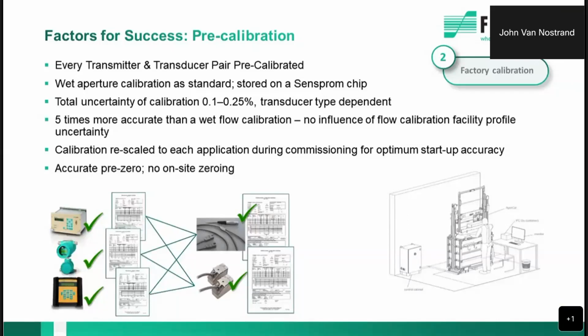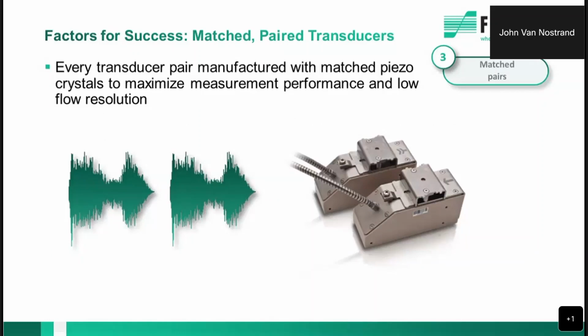Also the calibration. We calibrate every pair of transducers and every meter before we ship them. And they come with a NIST traceable certificate that is in adherence to the 17025 standard. And that's, like I said, NIST traceable. So there's no need to set zero in the field. You have accuracy of plus or minus 1% of the flow rate. And the spec for repeatability is 0.15%. So you get a very accurate flow measurement right out of the box that you don't have to tamper with. So we have FLEXIM.